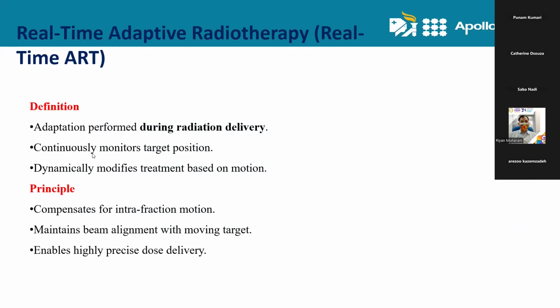It dynamically modifies treatment based on motions. Its main principle is to compensate for intrafraction motion, maintaining beam alignment with the moving target and enabling highly precise dose delivery.